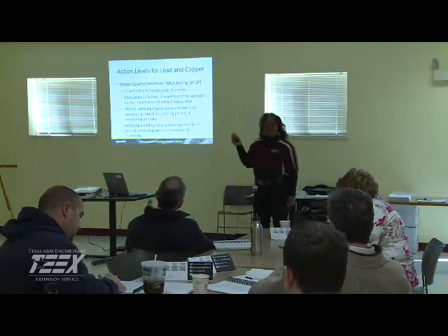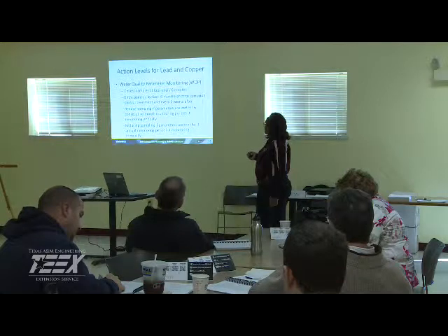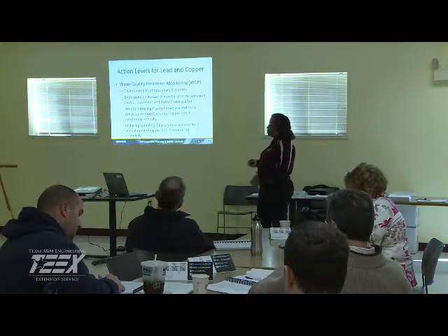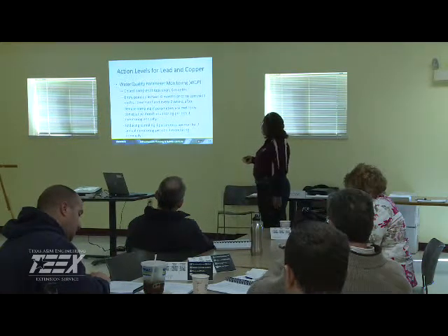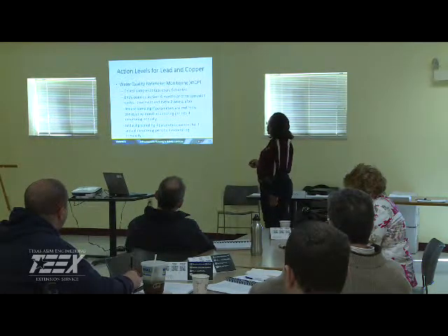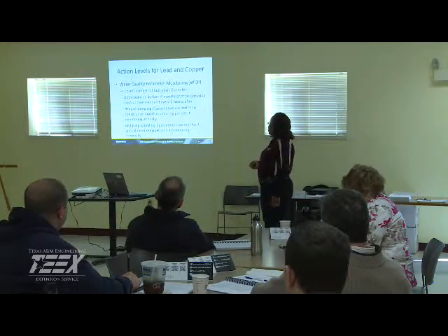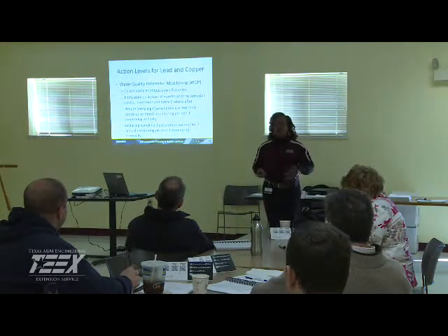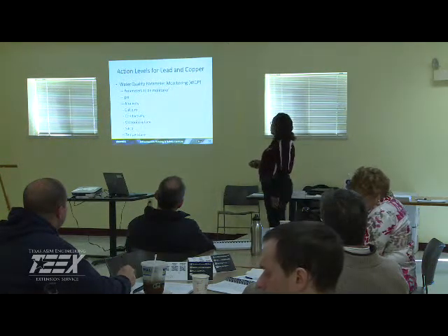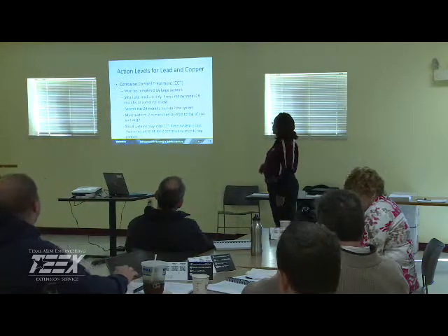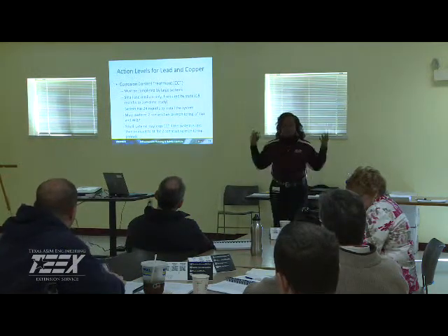If we're on reduced monitoring or sampling, again, we can only get there if we show that we're meeting our limits for at least 6 consecutive months of monitoring, if monitoring annually. Reduced sampling and parameters are for 3 annual monitoring periods if you're doing it once every 3 years. Those are the parameters, you've seen those before: pH, alkalinity, calcium, conductivity, orthophosphate, silica as applicable, as well as temperature.